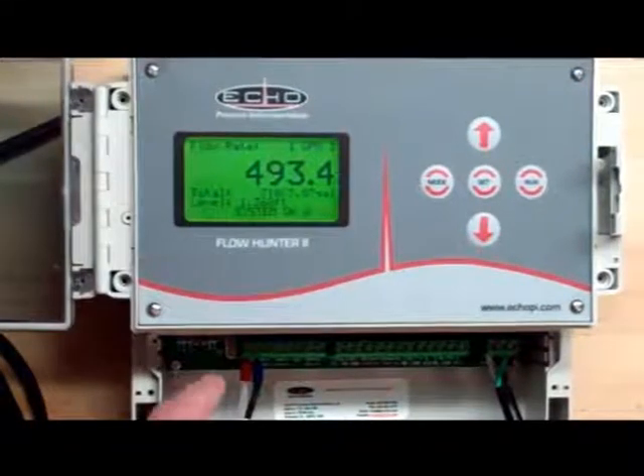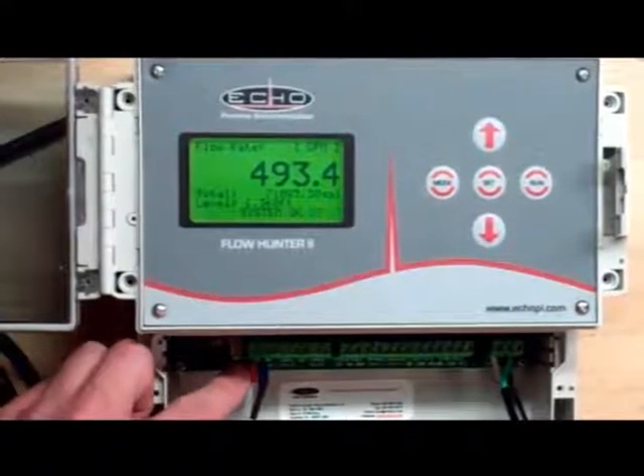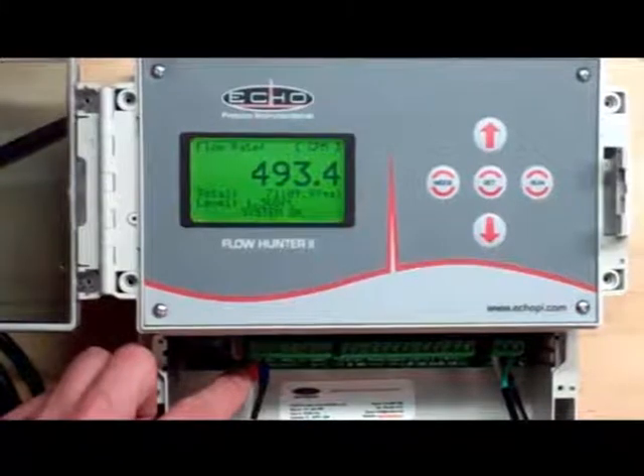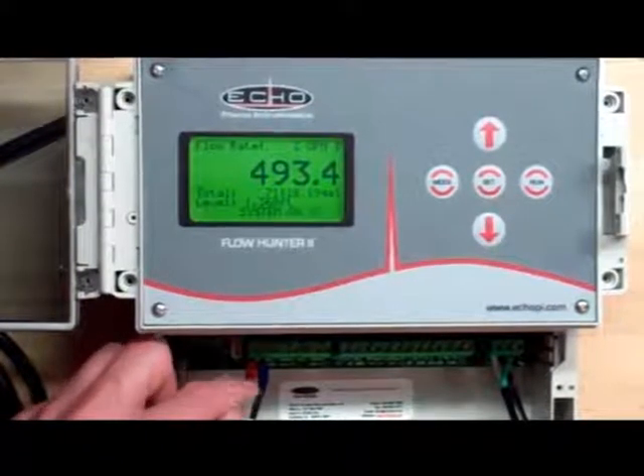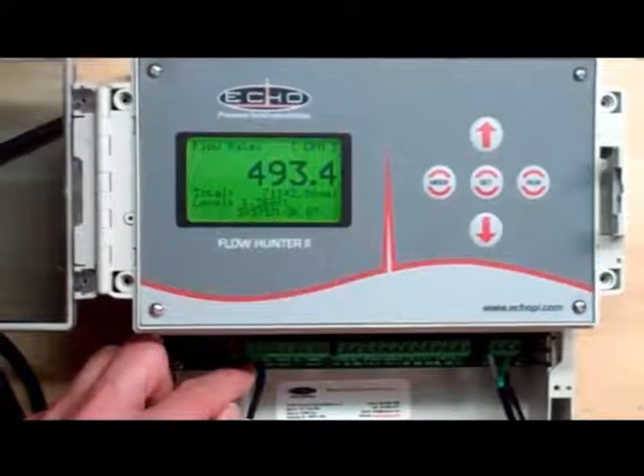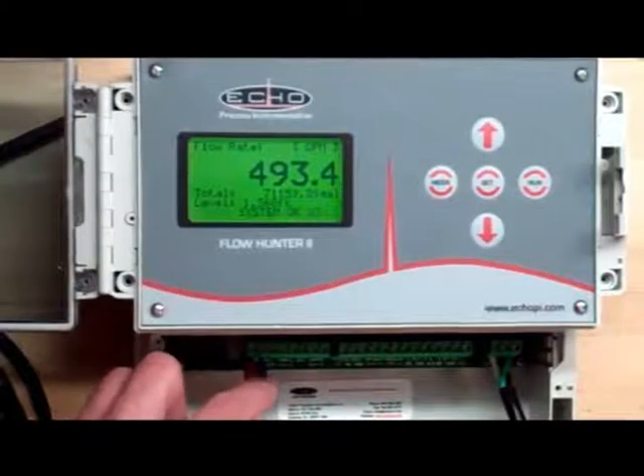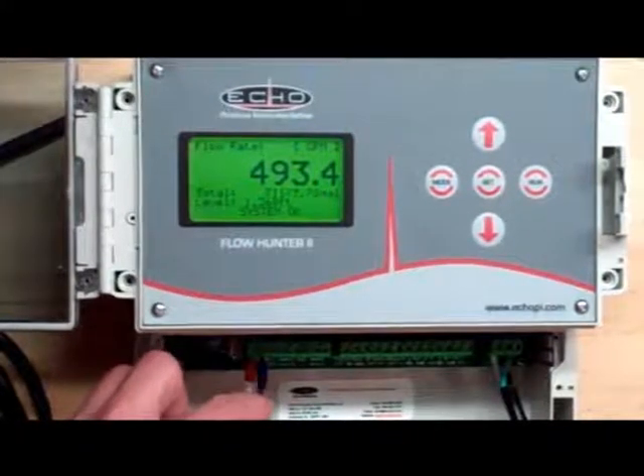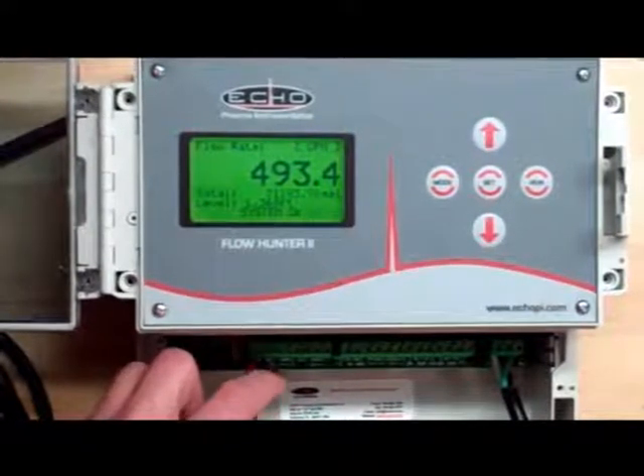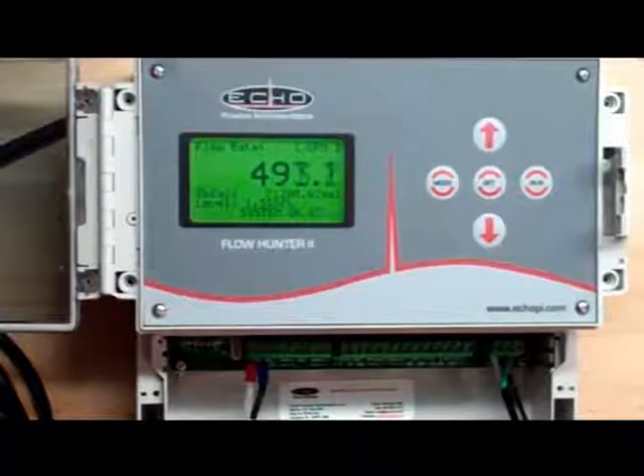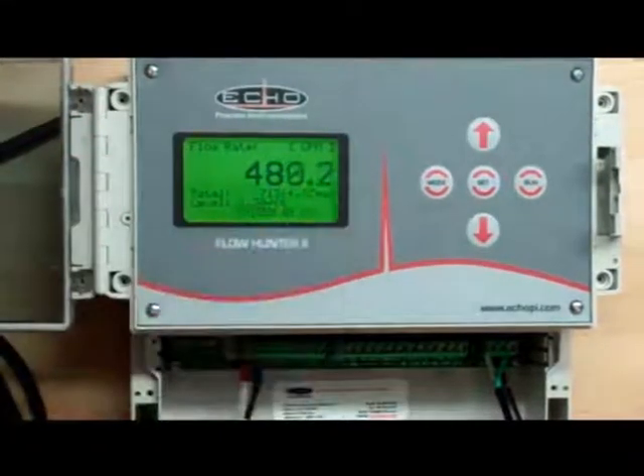Let's start out with the wiring here. In the very first terminal spot is the red, which is the core of the coaxial. It goes into the positive. And number 2 is the negative, which is blue, which is the shield from the transducer going to number 2. And right now it shows in gallons per minute.